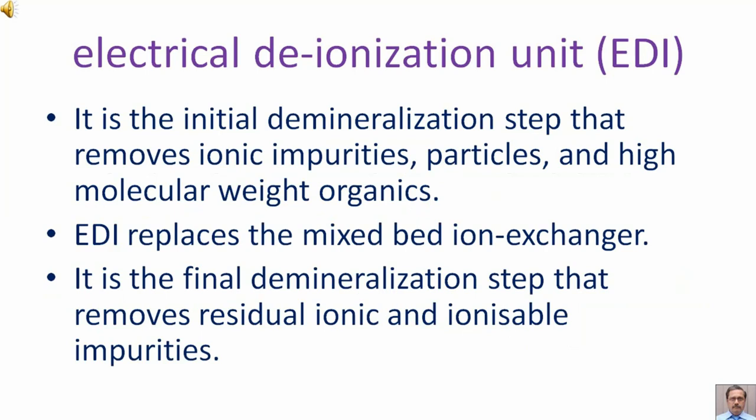It is the initial demineralization step that removes ionic impurities, particles, and high molecular weight organics. EDI replaces the mixed bed ion exchanger. It is the final demineralization step that removes residual ionic and ionizable impurities.